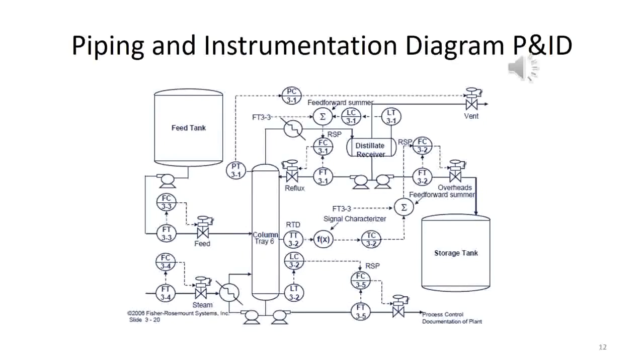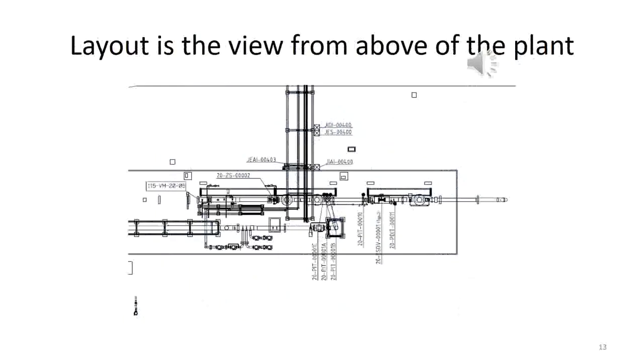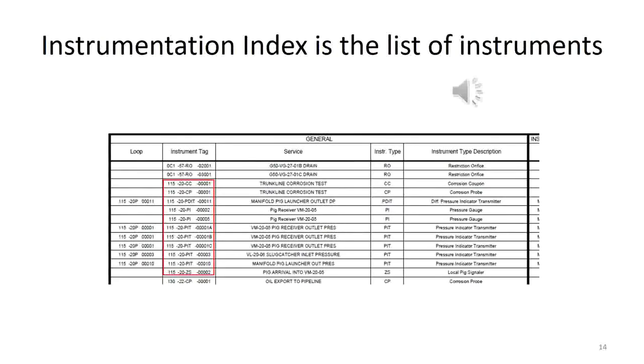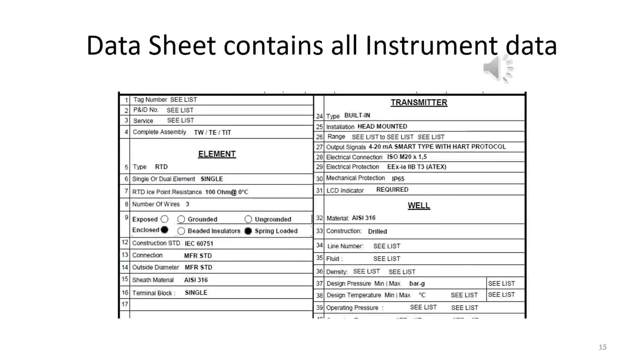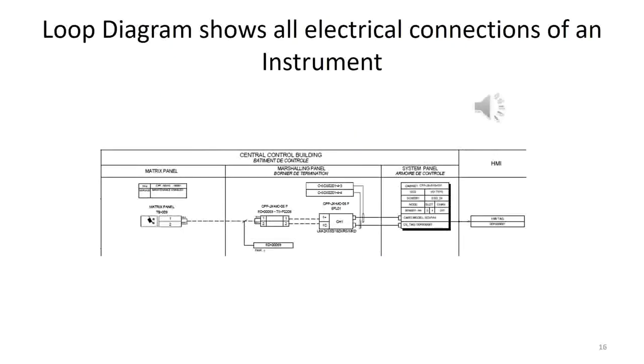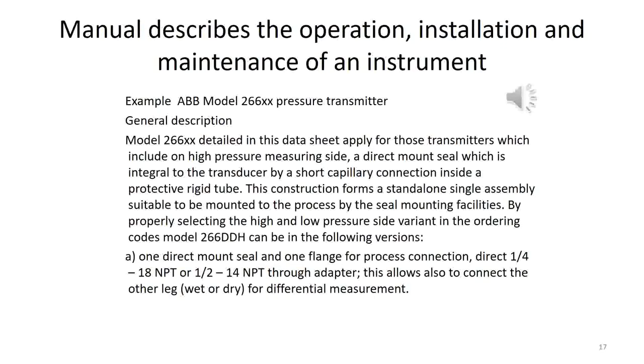A piping and instrumentation diagram, PID, is a schematic illustration of functional relationship of piping, instrumentation, and system equipment components. Layout is the view from above of the plant. Instrumentation index is the list of instruments. Datasheet contains all instrument data. Loop diagram shows all electrical connections of an instrument. Manual describes the operation, installation, and maintenance of an instrument. Below is an example of ABB Model 266 pressure transmitter.